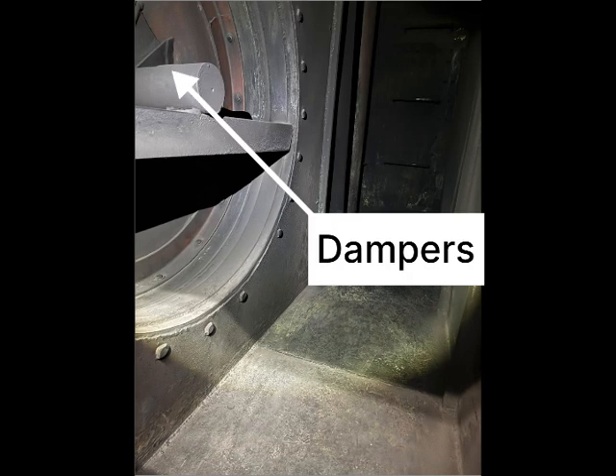After the hot smoke passes through the boiler, it then goes up through the economizer, which preheats the water. To use up the last bit of heat, the hot gas is passed through the air preheater, which preheats the air. Hot air helps the fires burn hotter. Draft to the boilers is provided by two fans that are powered by electricity, and air flow is controlled by dampers.